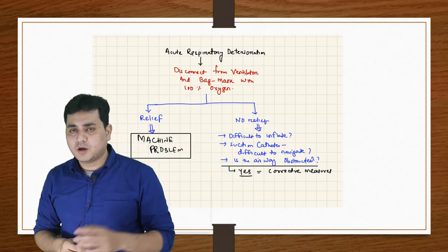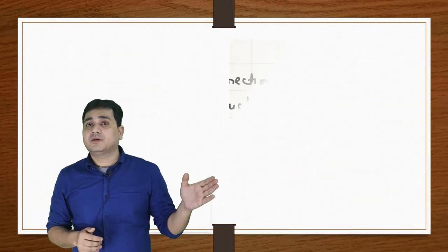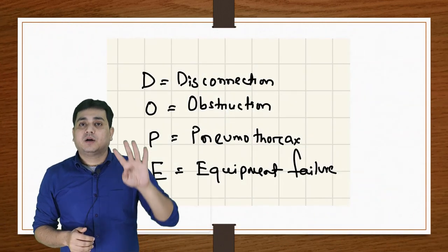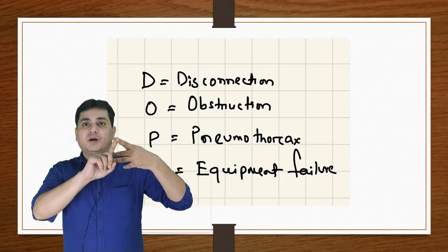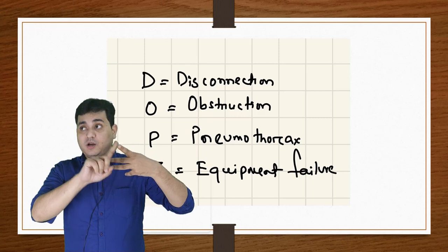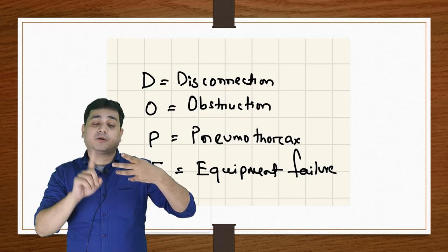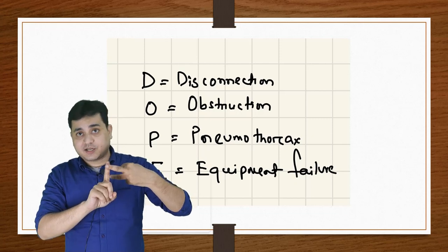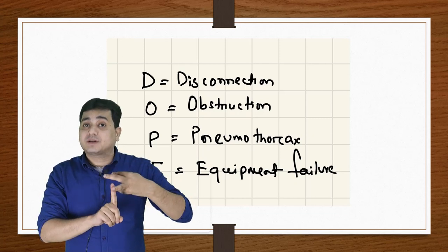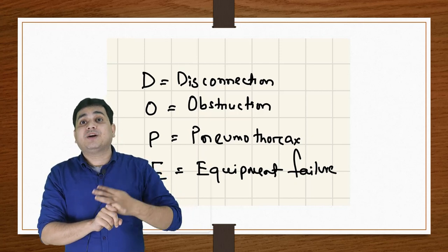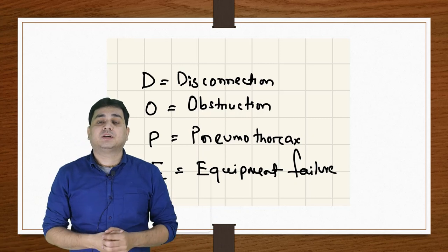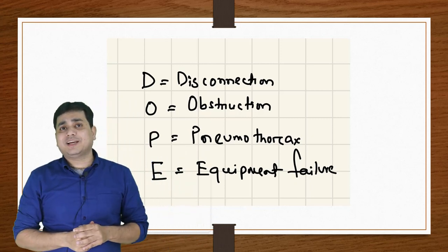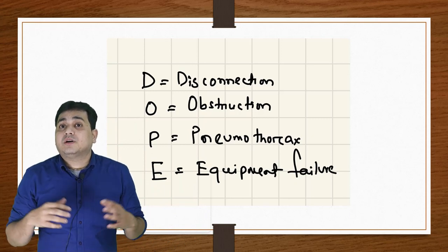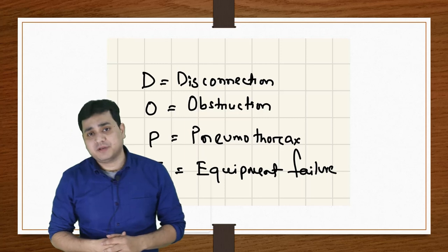Another very simple method is the DOPE technique. Whenever there is respiratory deterioration or high peak airway pressure, these four things have to be checked sequentially. D for displacement or disconnection: displacement of the ET tube, disconnection of the ventilator circuit. O for obstruction: kink, blood clot, secretions, tube blocks. P for pneumothorax, a compliance problem. E for equipment failure, where the ventilator has failed completely. This is a very simplistic technique in the beginning, but the differential is actually larger, so we have to keep thinking about what has happened to my patient. This is how we deal with the peak airway pressure alarm.